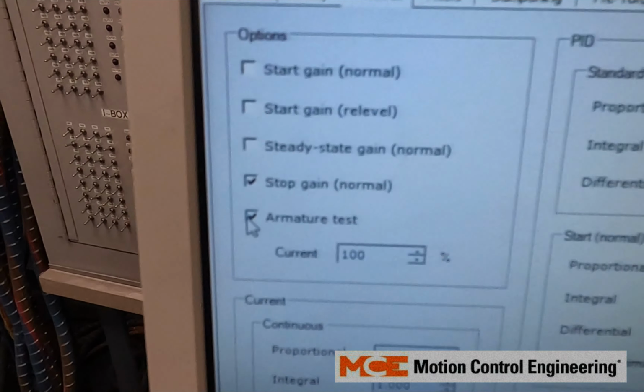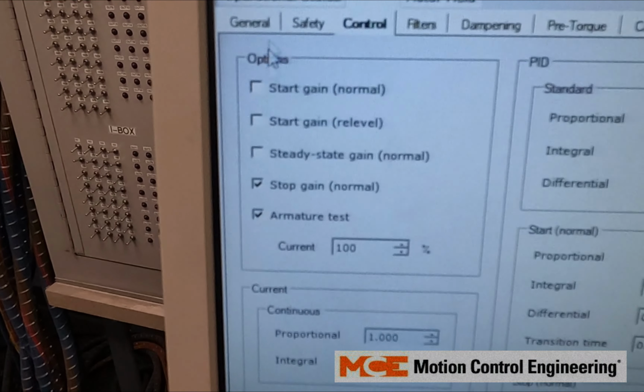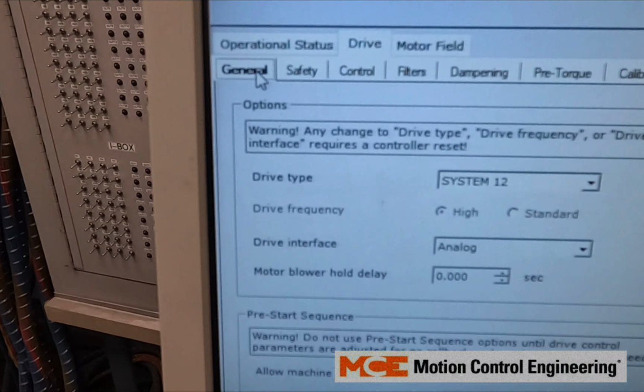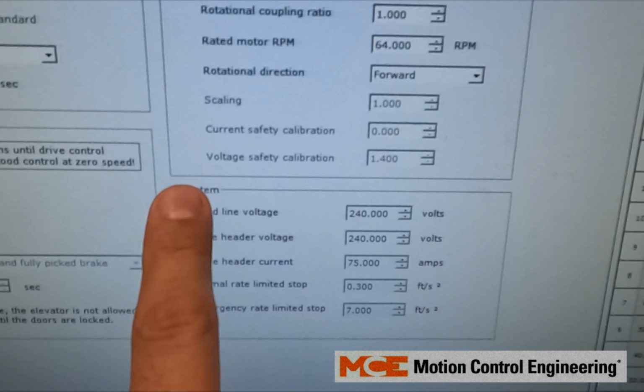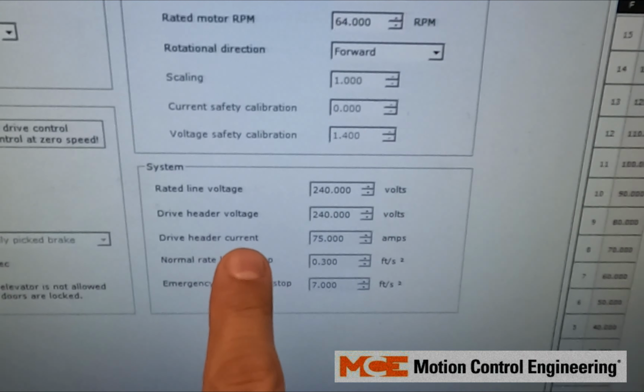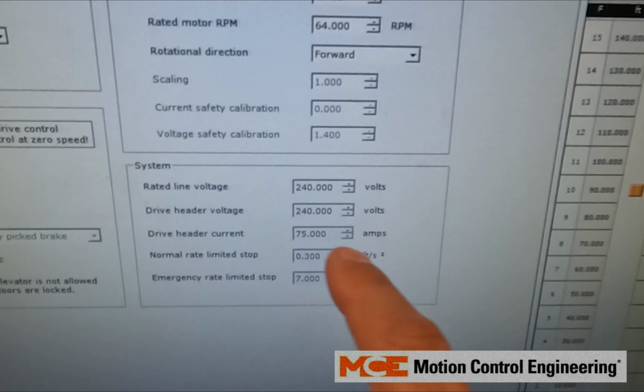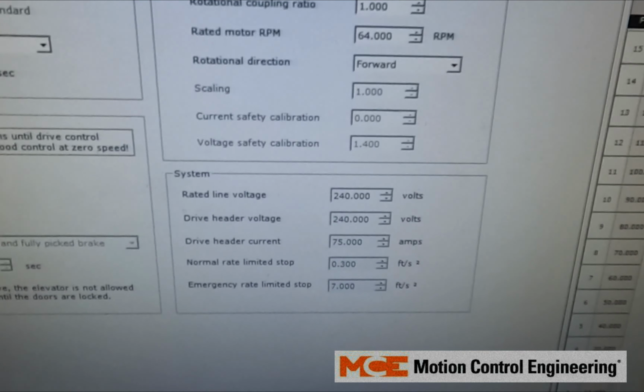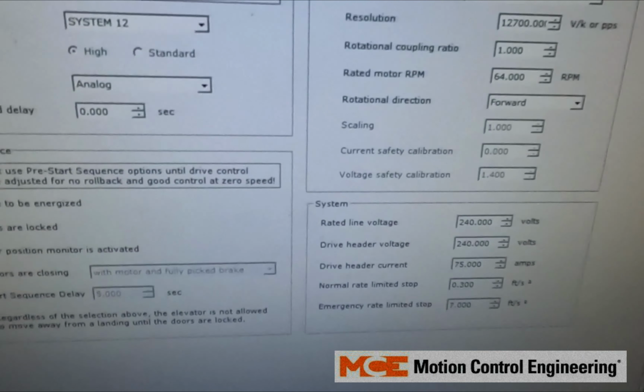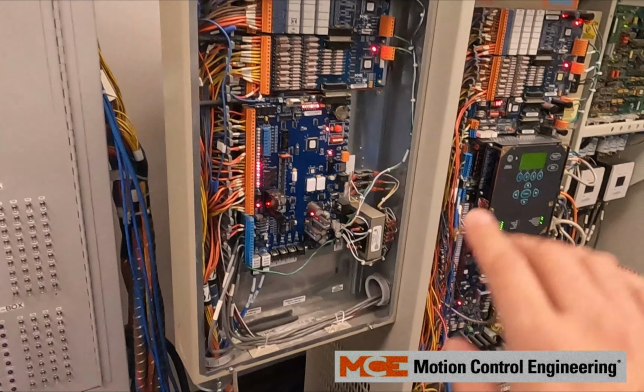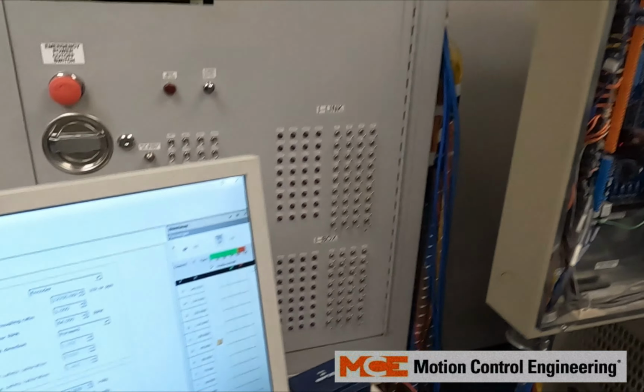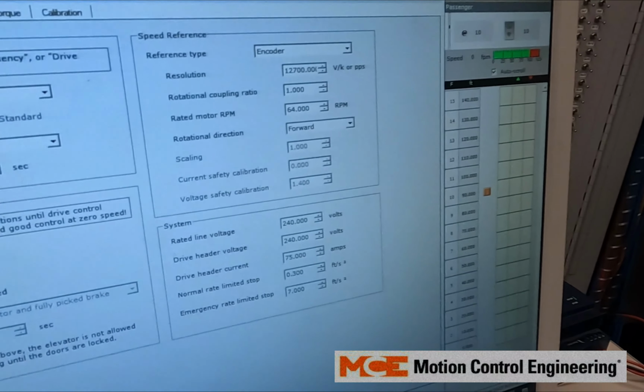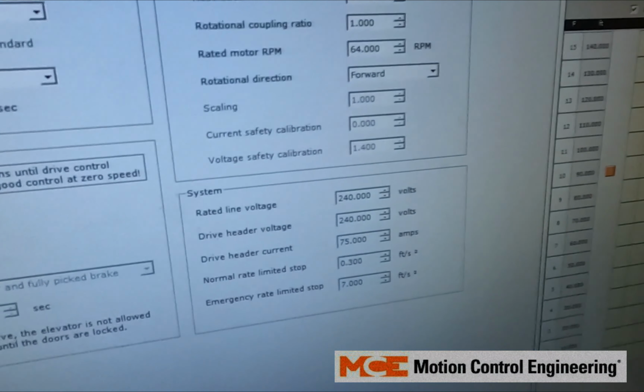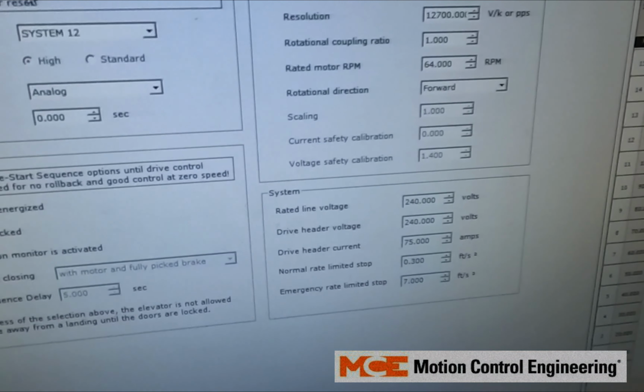So, according to our configuration, the system at 100% should be outputting 75 amps. So we should be sending a current command to your SCR drive for 75 amps, and we should also be getting that feedback back to our controller.